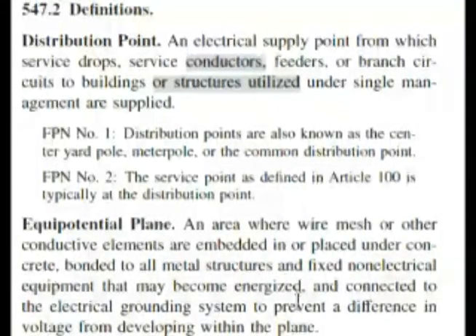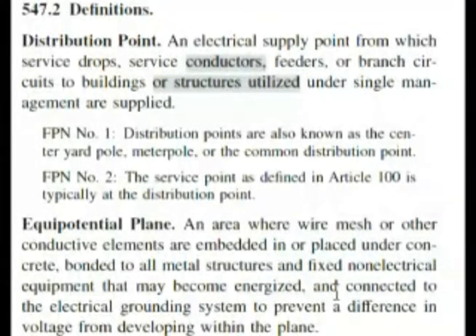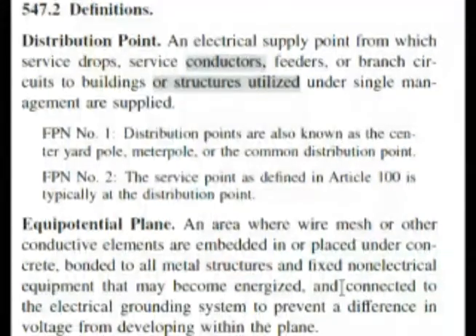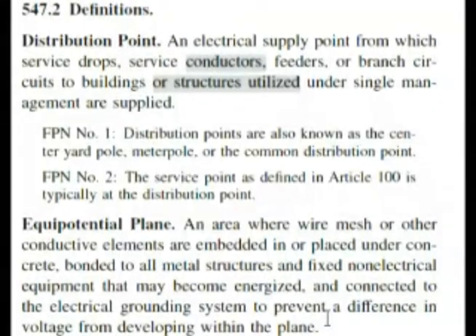And if we get down here, under equipotential plane, we find out that it's almost word for word what our question is asking. It states: connected to the electrical grounding system to prevent a difference in voltage from developing within the plane. Our question asked if that is the purpose of the equipotential plane — this makes True the correct answer for our test.